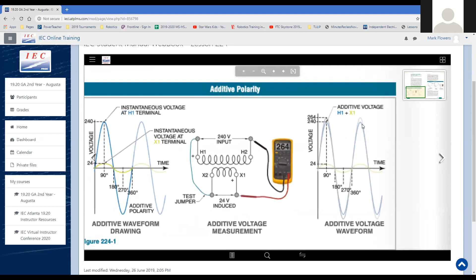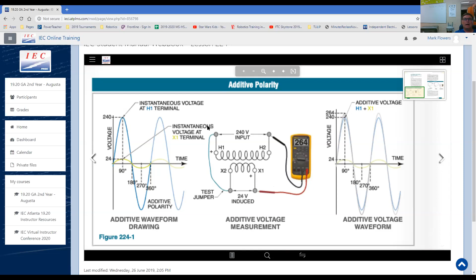Sometimes if you need 240 or more, you can add this extra transformer, just like the little small one I have. You add one more, and you see how they're tagged together, H1 to X2, H2 to X1. You'll notice it has 264 volts of the additive measurement. That's 240 on the first one from the primary, and you got 24 more induced from this one, and you can use that as an additive amount of voltage. Why would you do that?